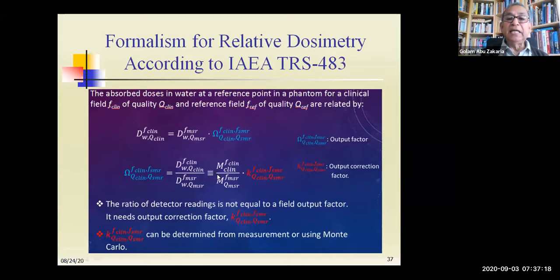You see, in the German DIN norm, they suggest any small dosimeter, like a diode or diamond or pinpoint chamber, you can use as a reference dosimeter. It is just a difference from the IAEA protocol. The IAEA protocol allows only an ionization chamber, but in the German protocol, you can use any small tiny chamber when you have calibrated it in your hospital. So this is relative dosimetry.